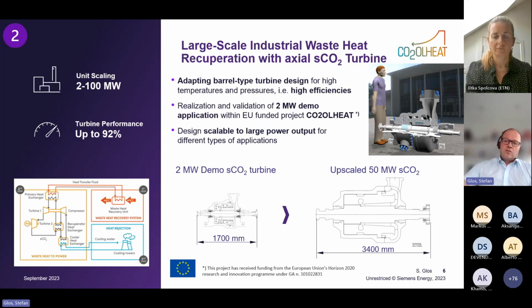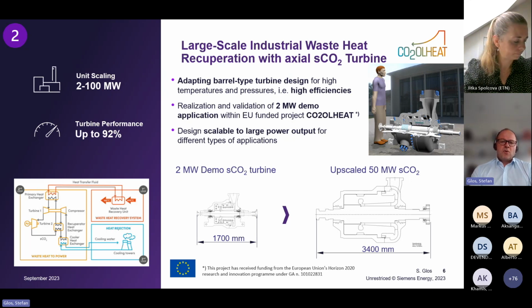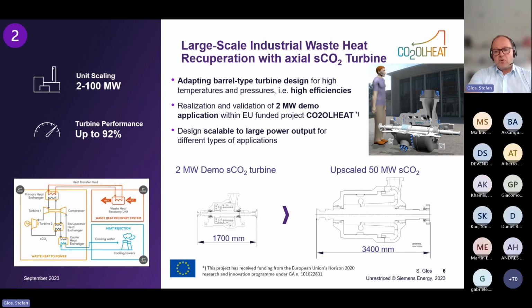As already mentioned, within this European-funded CO2OLHEAT project, we have designed a high-pressure barrel-type turbine for sCO2. The goal is the realization and validation of this demo plant. Unfortunately, this project is still on hold, but we are working on further progress. We always had in mind a design which is scalable to larger power output, and we did that exercise, which is roughly shown on the lower end of this slide. For 2 megawatts, we get a rotor length of roughly 1.7 meters, and if we scale that up to 50 megawatts, for instance, we have a shaft length of only 3.4 meters.